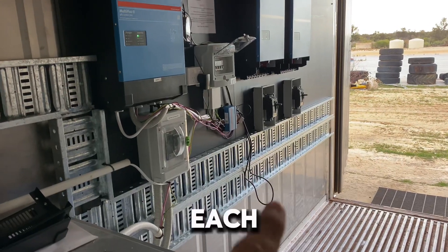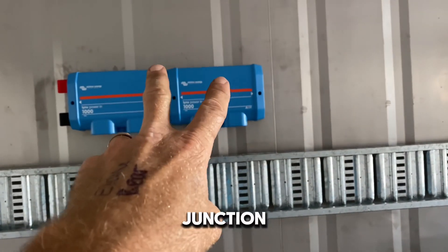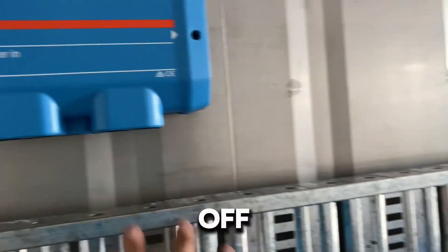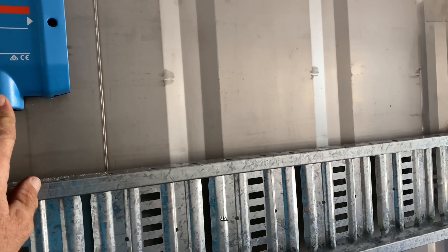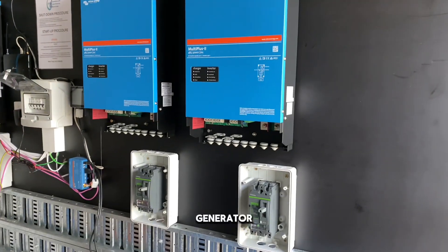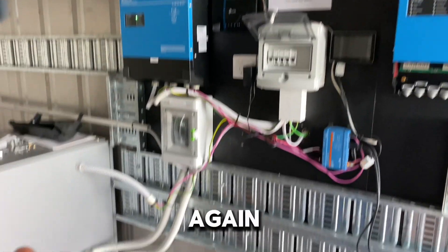There'll be DC isolators under each inverter as well — a lot of isolators, but it's the correct way to do it. My DC cables from the battery cabinets will run into the Lynx busbar junction, and then each cable run to the inverters needs to be the same length, which is a bit tricky when they're not all the same distance apart. I'm using three of the four terminals, leaving one spare for future solar via MPPTs, since at the moment the system is charged by generator.